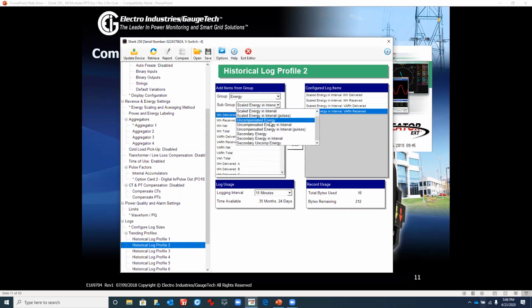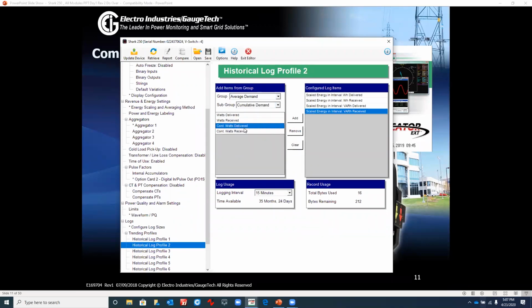And I could go through all the others, but it's basically a similar configuration, similar meaning for each one. In this particular log 2, we chose log 2 to be scaled energy. But you have a choice of many options to choose from. In the screen also, you see you have your max and min. You could also program with your voltage and current. You have an enormous amount of information that you could capture. You have average demand values, and a lot of information again you can store in the meter on those in your programming. Cumulative demand, you have watts delivered, watts received. Those are your 4 choices. And timestamp, I've never used that one, but you could also profile or capture demand last reset times and store that in the meter.